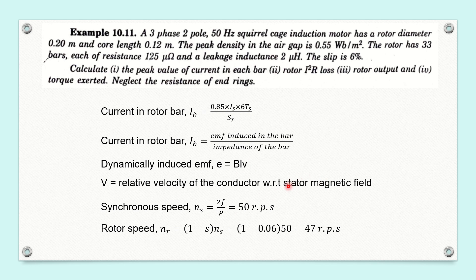Let us calculate the velocity of the stator magnetic field. We calculate the rotational speed in RPS. We know the stator magnetic field revolves at synchronous speed, and synchronous speed is 2F/P in RPS. Frequency is 50 Hz and number of poles is 2, so it will be 2 × 50 ÷ 2, which is 50 RPS. This is the revolution speed of the stator magnetic field.